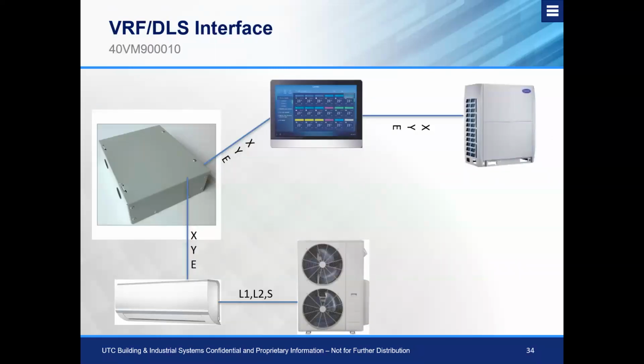Another option that we want to talk about with the Carrier VRF system is our VRF ductless interface. This interface utilizes our centralized controller that not only can connect our Carrier VRF system, but it can connect Carrier ductless all on one centralized controller, which really makes controlling and monitoring the systems as simple as possible, because we have one centralized location where we can monitor issues or performance instead of walking the entire building itself. Certainly something to keep in mind, especially if you have a project that's going to have a mixture of VRF and ductless throughout the space. This is something you'd want to consider, and in my opinion, take advantage of to be able to monitor multiple style systems that are not just VRF.